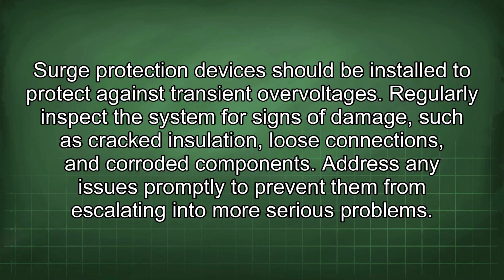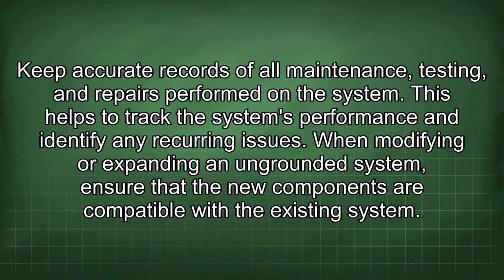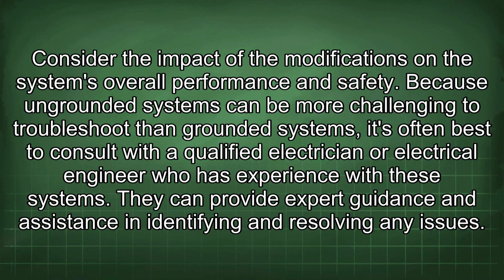Regularly inspect the system for signs of damage, such as cracked insulation, loose connections, and corroded components. Address any issues promptly to prevent them from escalating into more serious problems. Keep accurate records of all maintenance, testing, and repairs performed on the system. This helps to track the system's performance and identify any recurring issues. When modifying or expanding an ungrounded system, ensure that the new components are compatible with the existing system. Consider the impact of the modifications on the system's overall performance and safety.